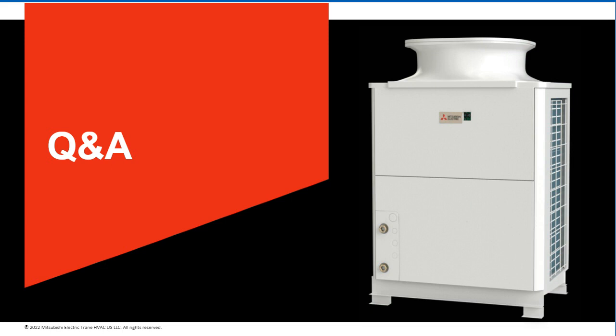So in warmer climates, can the secondary heat exchanger be eliminated and domestic water run through the internal refrigerant-to-water heat exchanger? The problem with that is that the secondary heat exchanger is about a $500 to $600 heat exchanger, and you wouldn't want to compromise the cost and complexity of the heat pump water heater itself. And that's why there's the primary secondary loop, is that you wouldn't want to risk the integrity if you had bad water quality. So is it possible? Sure, but it's risky. Yeah, and just for now, we're not going to allow that removal of the secondary heat exchanger, regardless of the climate, just to make sure we get longevity out of the systems overall.